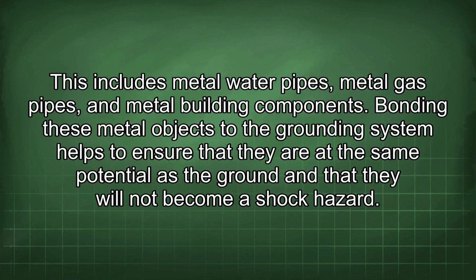Fifthly, bond any metal objects that are likely to become energized to the grounding system. This includes metal water pipes, metal gas pipes, and metal building components. Bonding these metal objects to the grounding system helps to ensure that they are at the same potential as the ground and that they will not become a shock hazard.